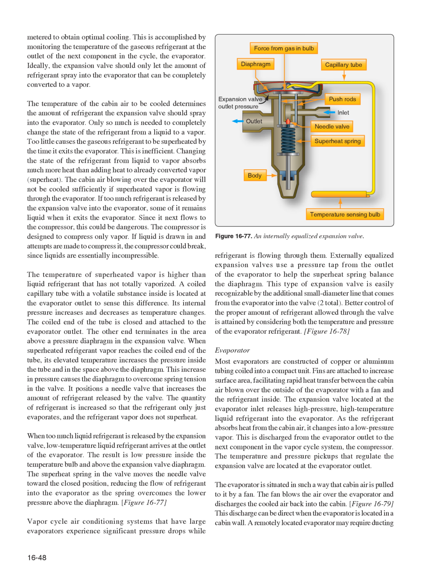The temperature of the cabin air to be cooled determines the amount of refrigerant the expansion valve should spray into the evaporator. Only so much is needed to completely change the state of the refrigerant from a liquid to a vapor. Too little causes the gaseous refrigerant to be superheated by the time it exits the evaporator. This is inefficient. Changing the state of the refrigerant from liquid to vapor absorbs much more heat than adding heat to already converted vapor, superheat. The cabin air blowing over the evaporator will not be cooled sufficiently if superheated vapor is flowing through the evaporator.